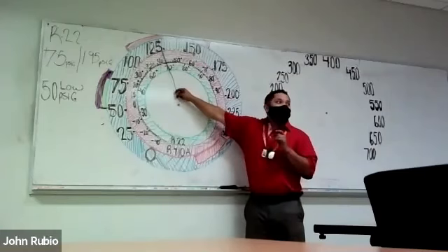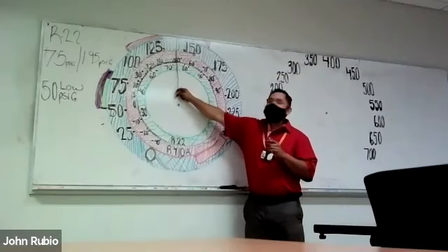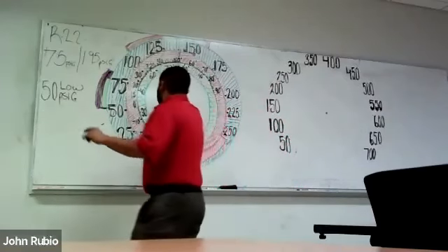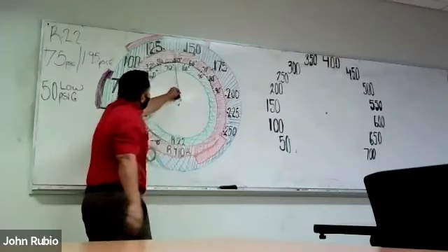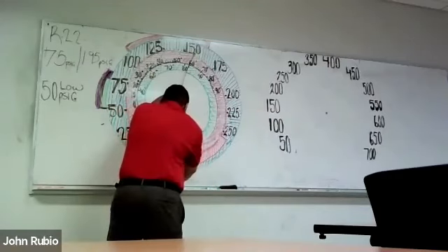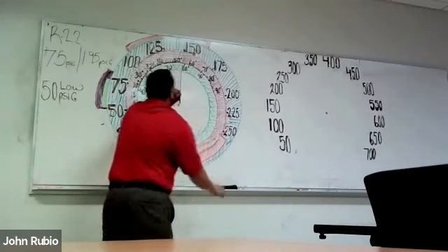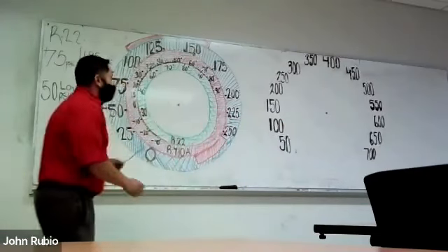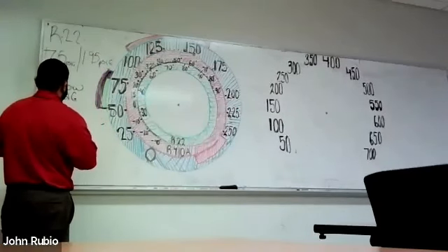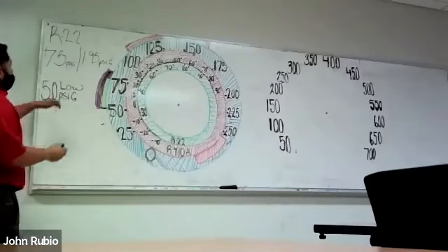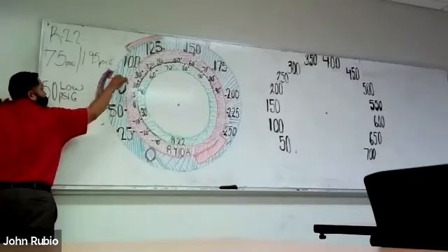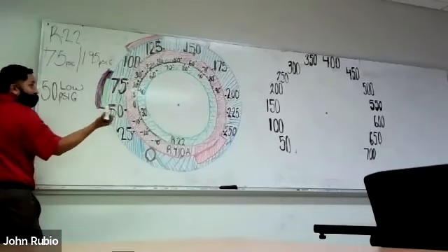But to find this improvement, it all starts with what's the temperature in the pink bar. From now on, when you write pressures down, you have to write the temperature too. You take advantage of every opportunity you have, whether it's a maintenance or a no-cool, to put your data down and show that you enter data. So if we're going to 75 PSIG for R22, when you see 75 PSIG, look down in the green bar, where are we? About 40 degrees.